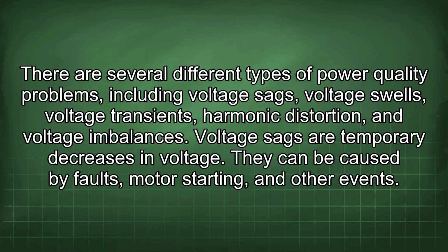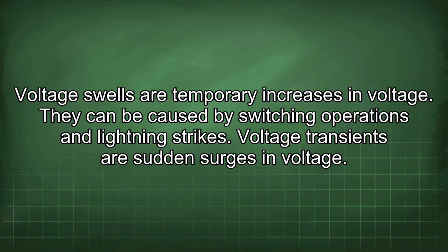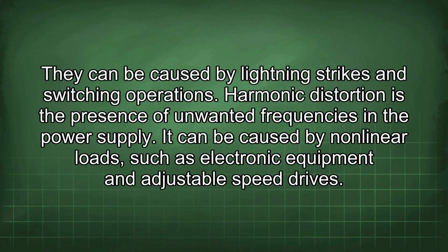They can be caused by faults, motor starting, and other events. Voltage swells are temporary increases in voltage. They can be caused by switching operations and lightning strikes. Voltage transients are sudden surges in voltage. They can be caused by lightning strikes and switching operations.